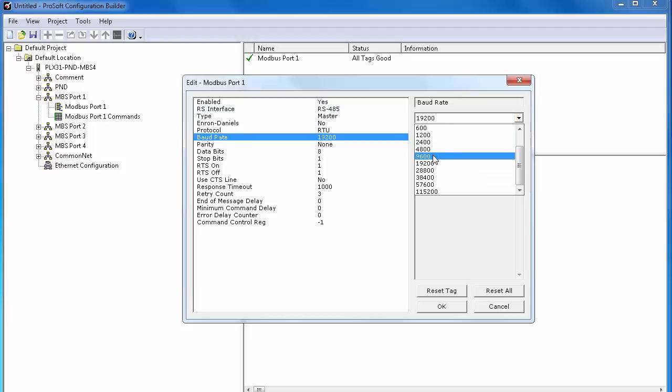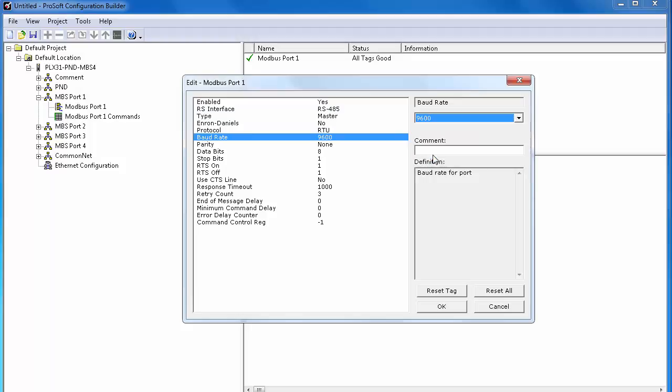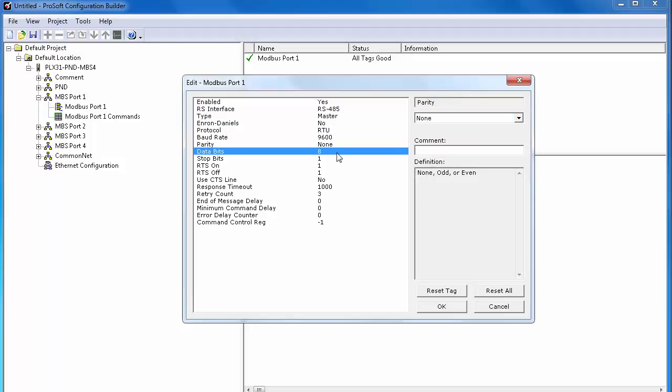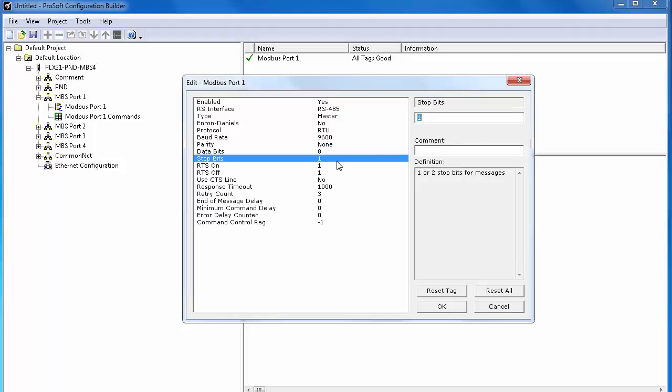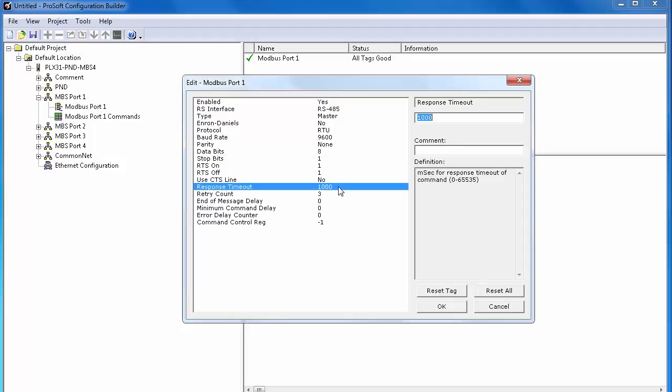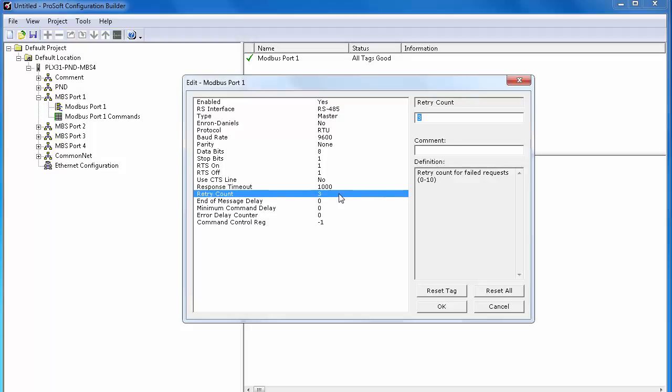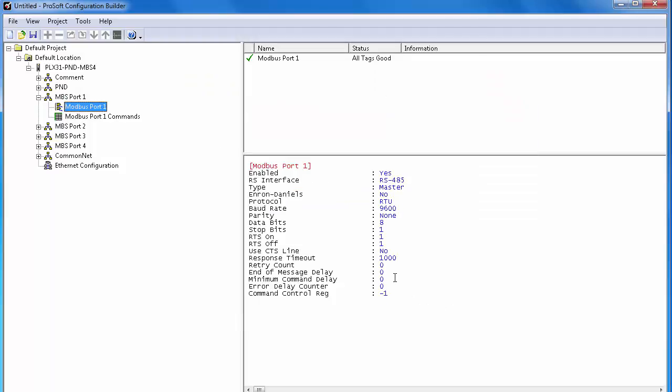Our baud rate will be 9600. Parity none. Data bits 8. Stop bits 1. You just need to make sure that all of these settings match those of your Modbus network. We'll leave response timeout at 1000. This is in millisecond increments, so this is 1 second. We'll set retry count to 0 so that if it misses a command, it won't retry it. It'll just grab it on the next queue. And once everything is set, we can click OK.